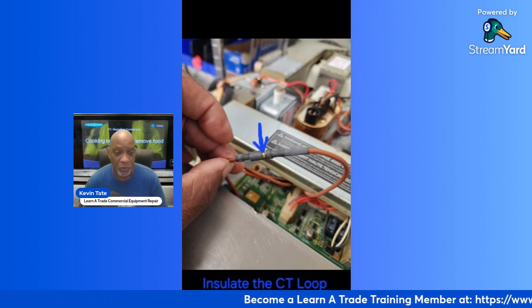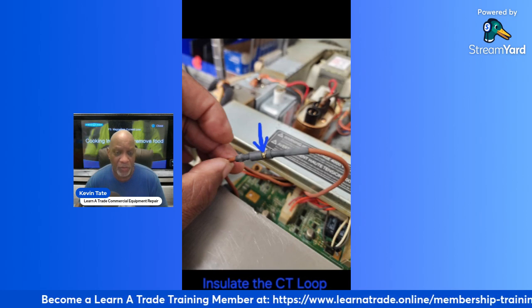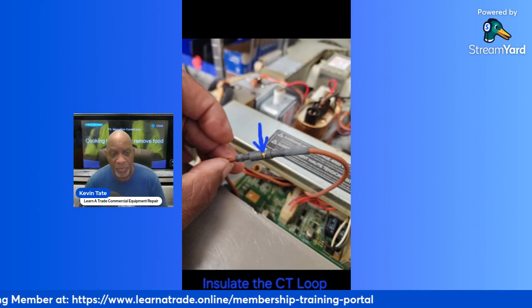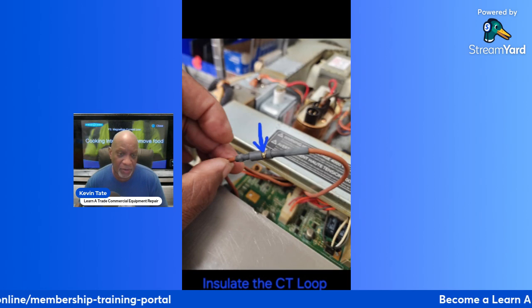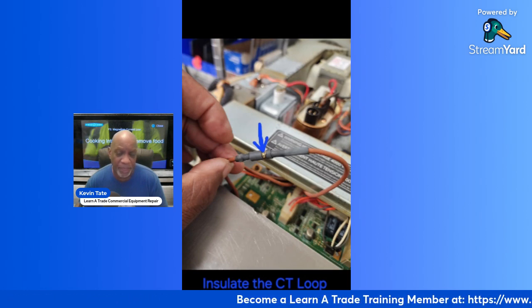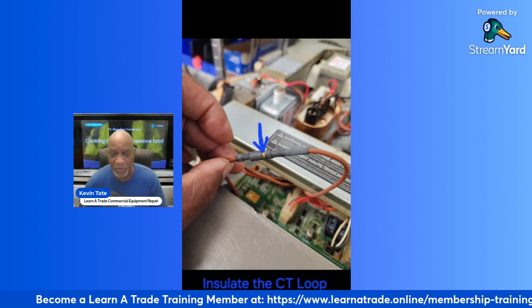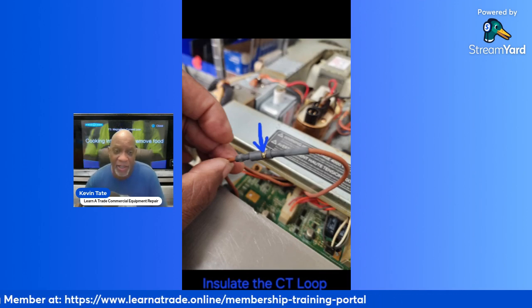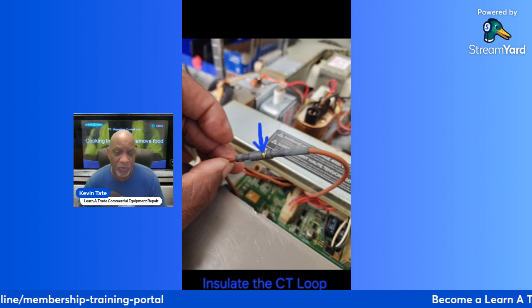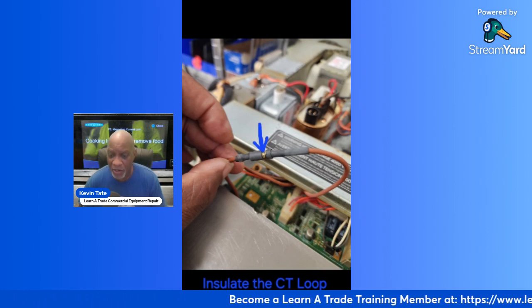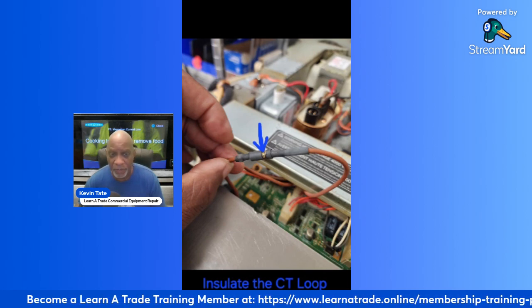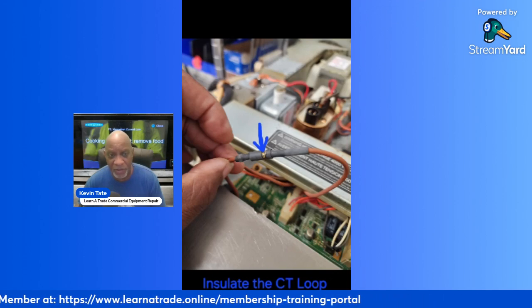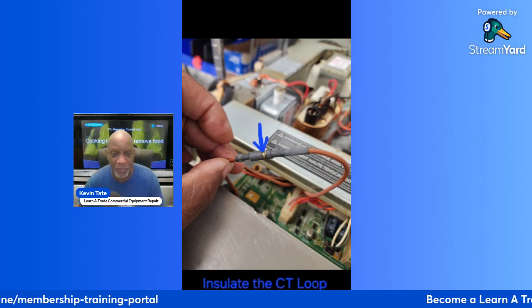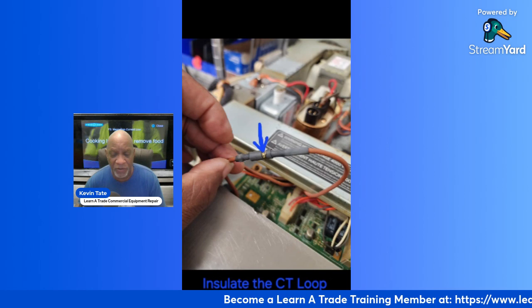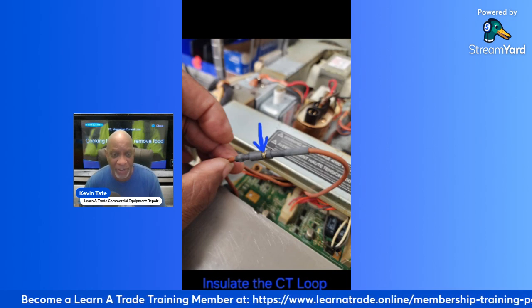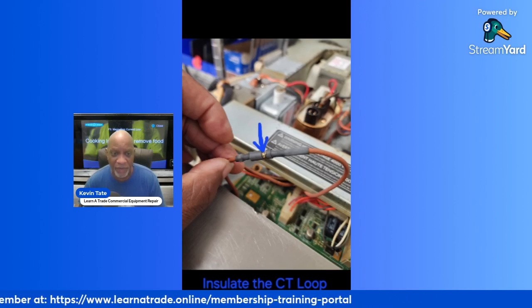Right here is the insulated CT loop. Okay, this right here is very common. Where you see the arrow at, the blue arrow is showing you an opening in the insulation that's over those terminals. And the thing is just to be on the safe side, especially when you're working with a unit that has over 2,500 volts going through it, you want to make sure that your wires are insulated and secured. This one here, even though it's a small opening, that's enough for you to get hit with electricity if you touch that, if that ends up touching to the metal brackets or to the body of the machine. So you want to make sure that you have that CT loop insulated.